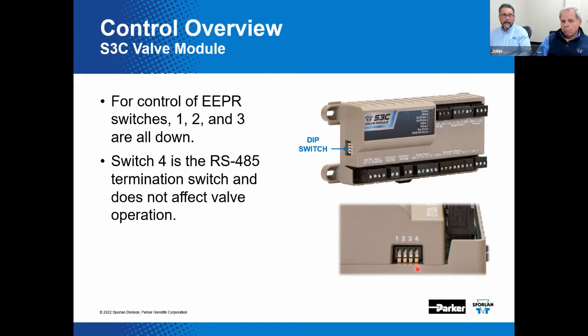Okay. There are obviously other combinations there. And it helps to identify and address the valve and configure to use an EEPR in the system. So typically this would be in conjunction with EEVs being used in that same system. And if you don't position those dip switches correctly to identify that type of valve to it, it's not going to control that valve correctly. It won't. Right. It will think it's something else other than what you want it to be.